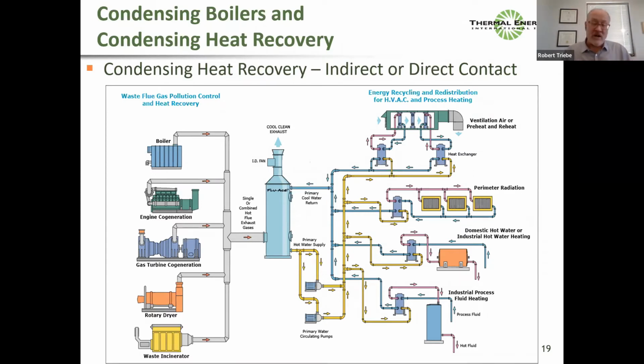However, you can very often recover heat from multiple sources and deliver to multiple sinks. You can really look at an economizer as a free hot water boiler. And that economizer provides you with free hot water. You could use multiple boilers, you could use multiple different process sources, and then you can deliver heat to your utilities. You can heat boiler makeup water, you can deliver heat to air heating, you can deliver heat to perimeter radiation, to reheats.